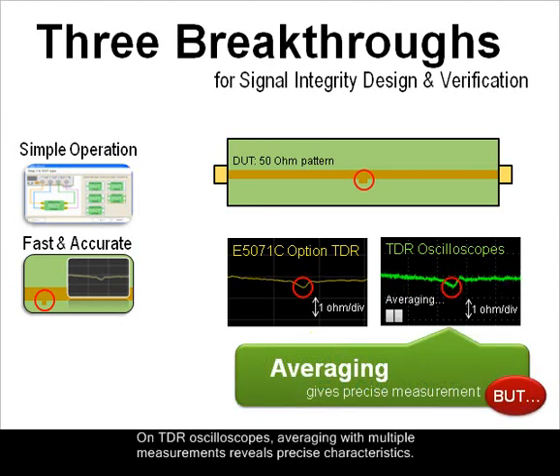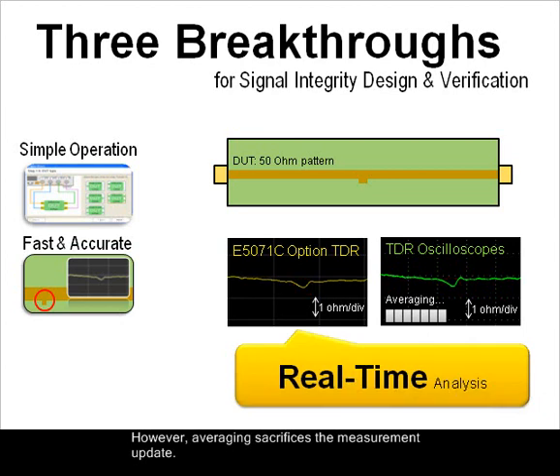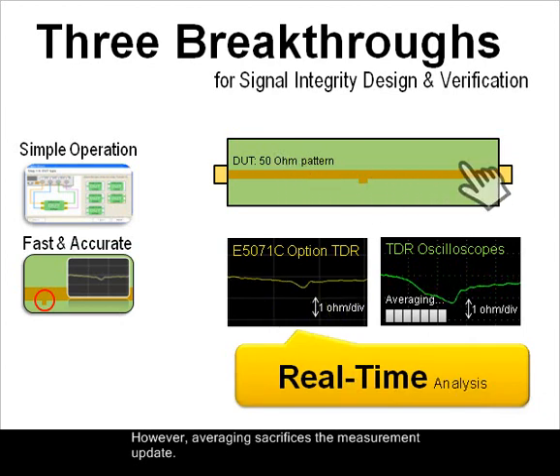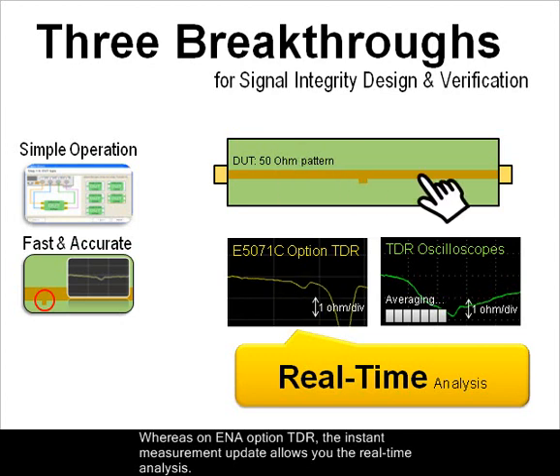On TDR oscilloscopes, averaging with multiple measurements reveals precise characteristics. However, averaging sacrifices the measurement update rate, whereas on the ENA Option TDR, the instant measurement update allows you real-time analysis.